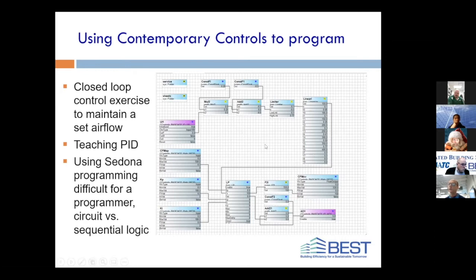Right now we are running the sequence where the students are driving an input with the differential pressure sensor, doing a linearization, giving an airflow, and then able to play with the PID, or at least the PI portions, and see real time. We've got the air handler up and running, so we fire that up, and it's on a PID, so we can hear that ramping up and down and oscillating, and they can adjust that, or we adjust that, and they go to each box and adjust their PID, and we can watch it go up and down. It's kind of exciting to see that we actually can start teaching PID with something with real feedback.